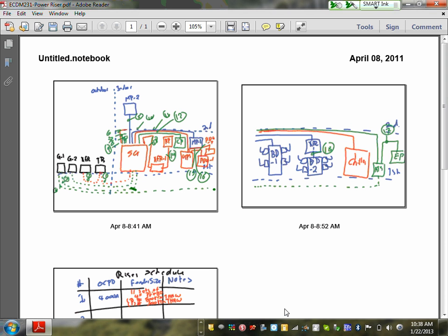We can incorporate them in our gear if you bonded this. In general, it's like a 25% add to the breaker price. 30. So it's not as bad as you think, for us. For some people it's more. But we could make this with four-pole breakers, and this could be bonded at that point. And we could switch neutrals, but it gets really ugly. So normally when you're doing this type of thing, you don't derive a system and you just use the service as a reference. Makes everything easier.